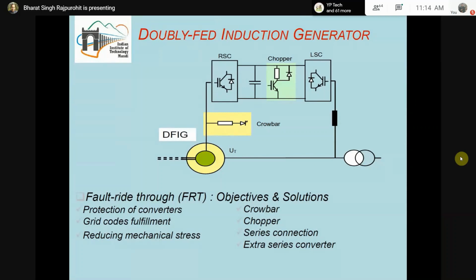Now let's see if a fault is happening in the grid. As soon as the grid has a fault, the current is going to increase in this rotor loop, and this may damage the power electronic converter. Now the question here is how the doubly fed induction generator is able to take care of this high current and retain its normal operation, or inject active and reactive power based on the grid connection requirements. The first method by which this can be controlled is a chopper which is connected to the DC link. This chopper has a resistance, and by operating this chopper based on the high current, the resistance can be utilized to dissipate this high energy, so that the DC link voltage and the current can remain limited in this rotor circuit.